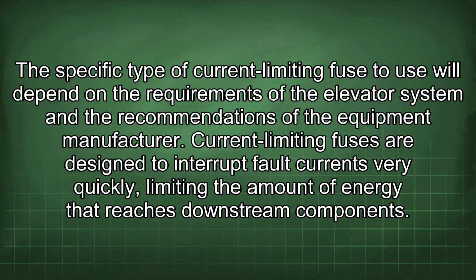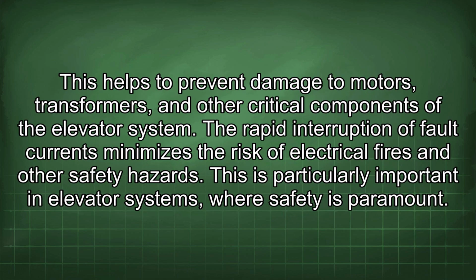The specific type of current limiting fuse to use will depend on the requirements of the elevator system and the recommendations of the equipment manufacturer. Current limiting fuses are designed to interrupt fault currents very quickly, limiting the amount of energy that reaches downstream components. This helps to prevent damage to motors, transformers, and other critical components of the elevator system. The rapid interruption of fault currents minimizes the risk of electrical fires and other safety hazards. This is particularly important in elevator systems where safety is paramount.